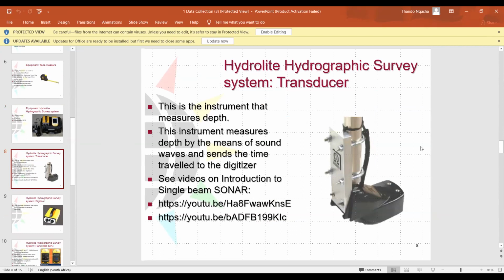As I told you before, the transducer collects the water depth. So this equipment will not be simply on the surface of the water. It needs to be deeper so that it is able to work. So the distance between the surface of the water, let's say the surface is here, and then whenever you go down to this, is your offset. We need a tape measure to measure this distance.